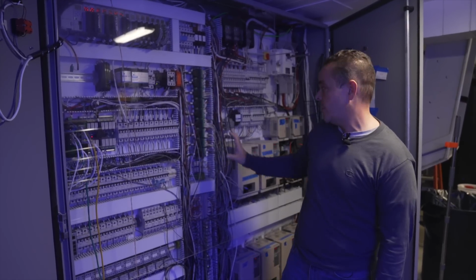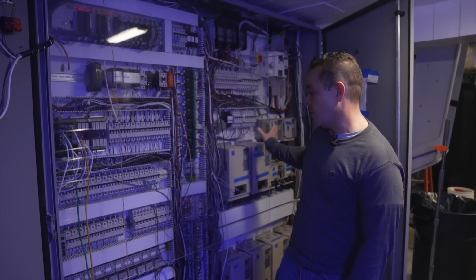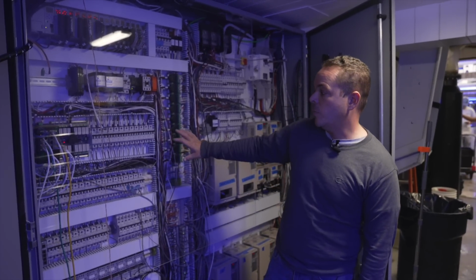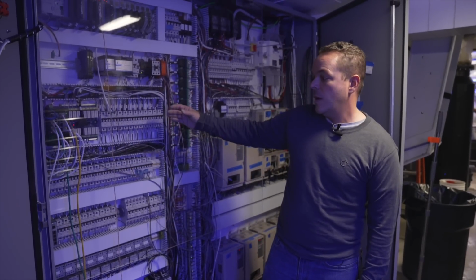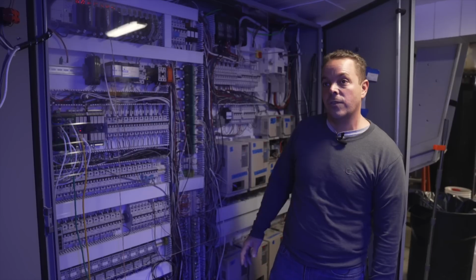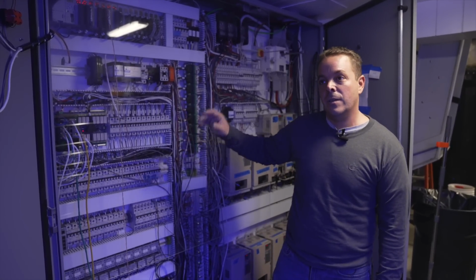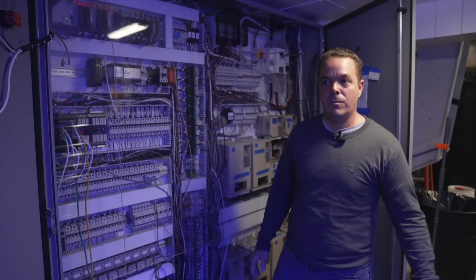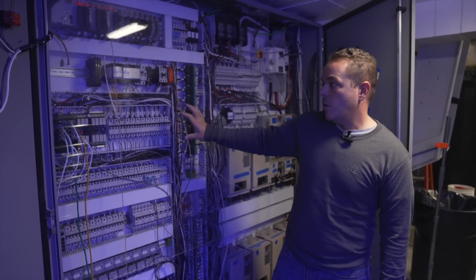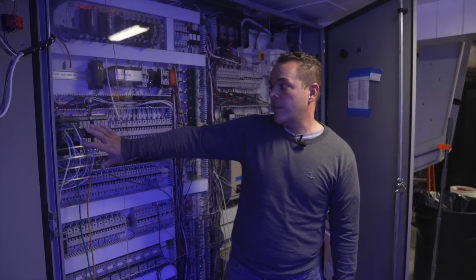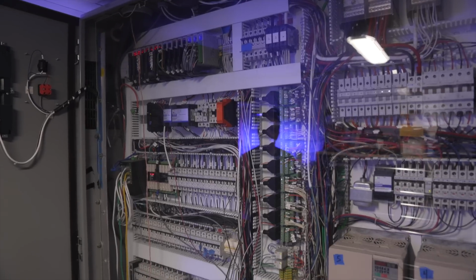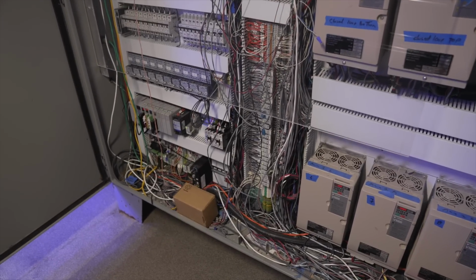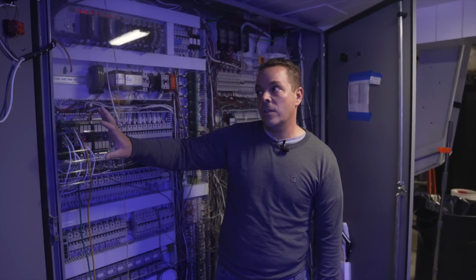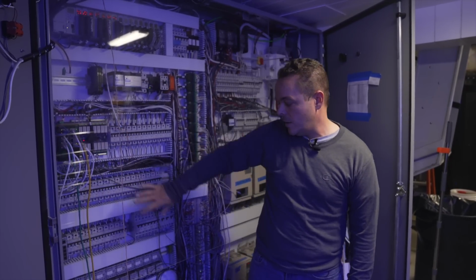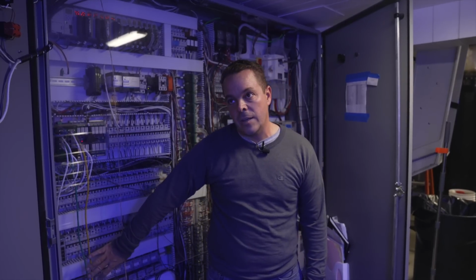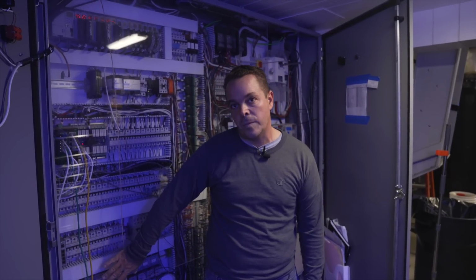We're also taking information from, like Andrew said, the generators and from the motor controls, which I'll explain in a second. We also monitor all the circuit breakers. So everything for the tank, with the exception of the condensers for the chillers, is powered from this panel. Every light, every pump, every little thing comes from here. So all the power is distributed from here. We also have the network for all the communications within the fish tank run to here. All those remote locations, the touch screens, the HMIs, all come back to here. All the smaller motors, like on the calcium reactors and sulfur reactors, are controlled by these relays here.